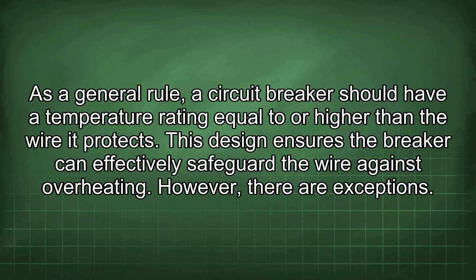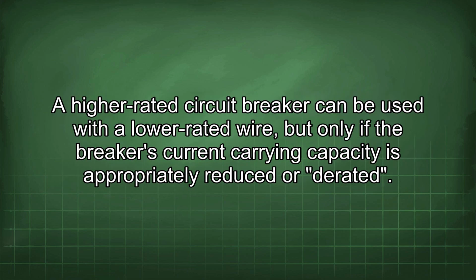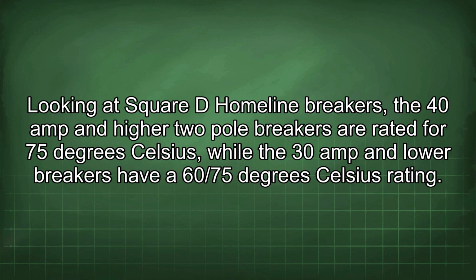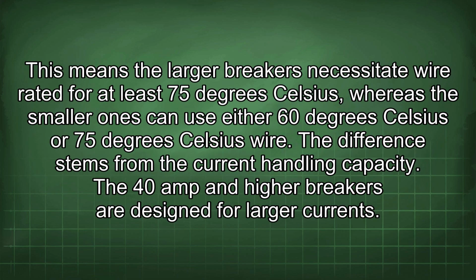However, there are exceptions. A higher rated circuit breaker can be used with a low rated wire, but only if the breaker's current carrying capacity is appropriately reduced or derated. Looking at Square D Homeline breakers, the 40 amp and higher 2-pole breakers are rated for 75 degrees Celsius, while the 30 amp and lower breakers have a 60/75 degrees Celsius rating. This means the larger breakers necessitate wire rated for at least 75 degrees Celsius, whereas the smaller ones can use either 60 degrees Celsius or 75 degrees Celsius wire.